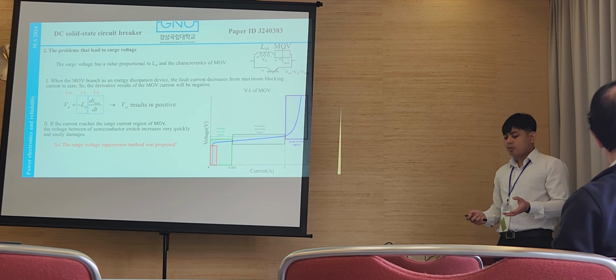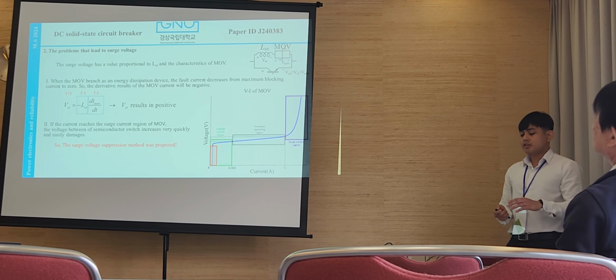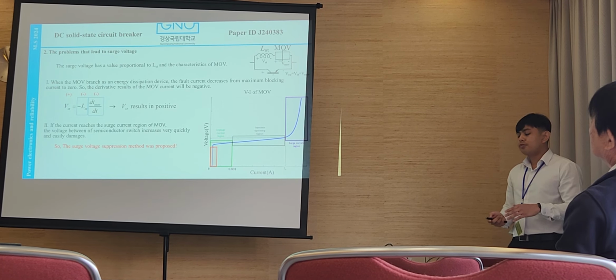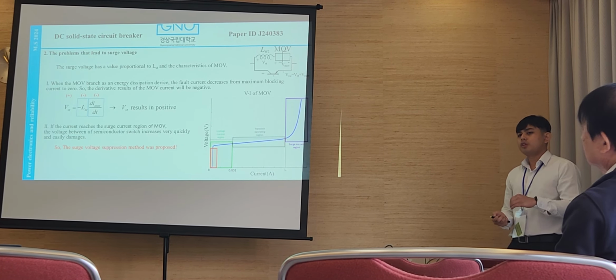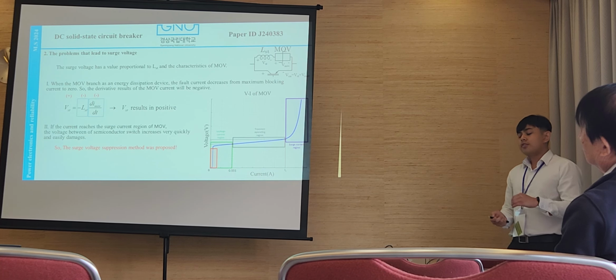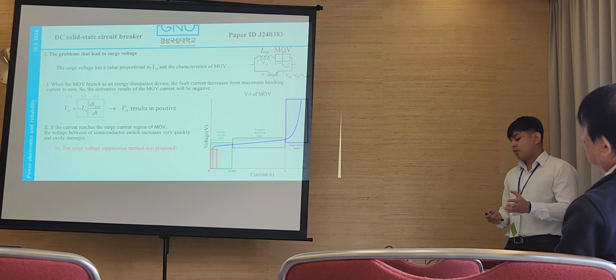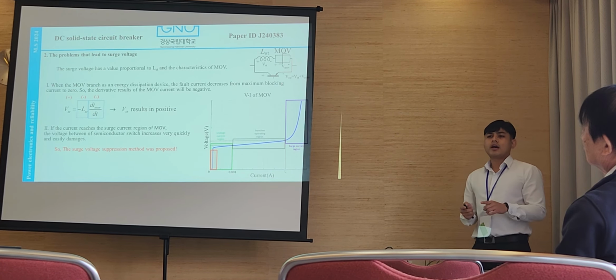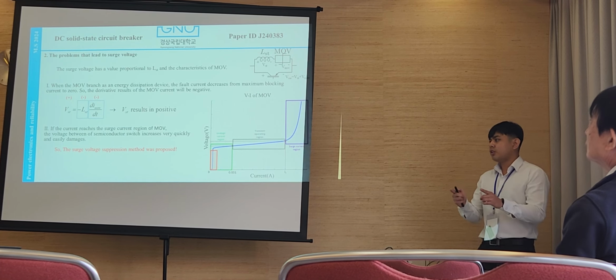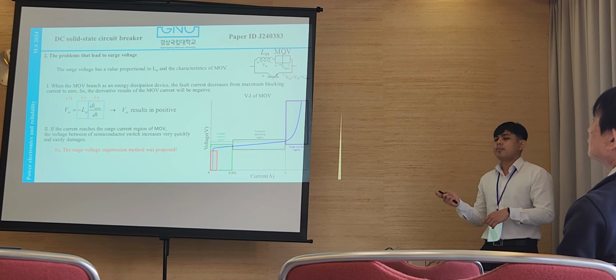First, when the MOV operates as the energy dissipation device, the fault current decreases from the maximum blocking current to zero. So the derivative of the MOV current results in a negative value, and you can calculate that the voltage across the stray inductance results in a positive value.